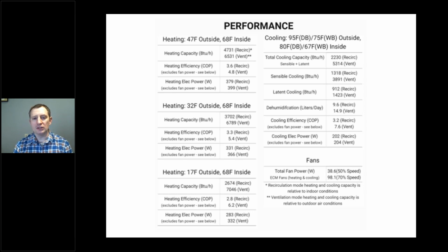The latent cooling is really set like an air conditioner. So the dehumidification is just part of its cooling function. So we can't specifically dehumidify like a standalone dehumidifier that's removing moisture while adding heat to the house.